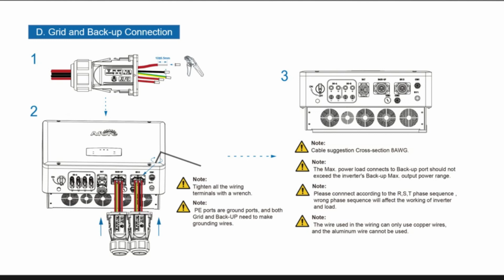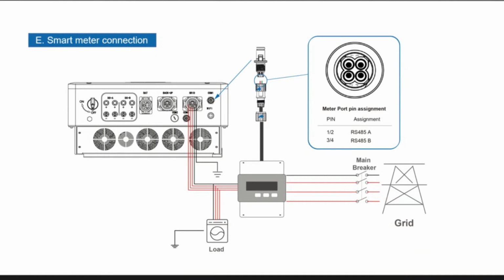As far as your connections on the top of here, you've got a backup circuit and you've got a grid connection on here. Your top connections on the front are your L1, L2 and L3, which are these here. L1 is this one, L2 is this one, and L3 is this one, so it goes from left to right. The two connections behind are your neutral and your earth connection. The earth connection is the one on the left-hand side behind, and your neutral connection is the one on the right-hand side behind. So make sure you get those right, please.